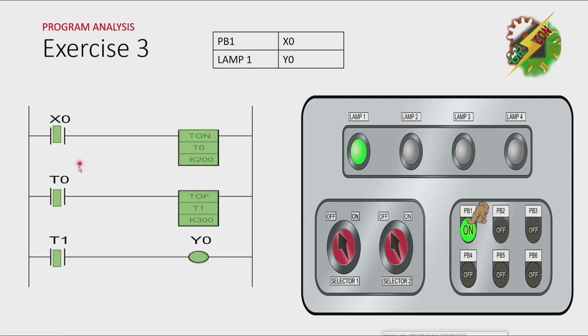Because T0 is activated, all the contacts of T0 will change. Because this one is normally open, it will close, and that will give signal to our timer here. And because this one is a timer off delay, it will immediately activate. Timer 1 here will change, and this one will give signal to Y0. Because Y0 is activated, lamp 1 will be turned on.